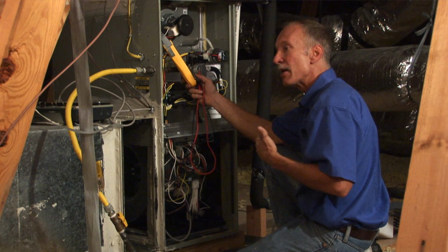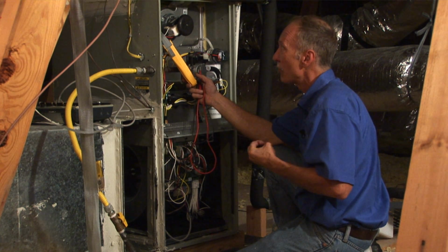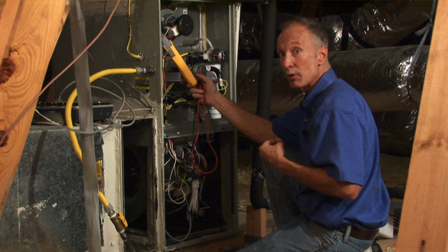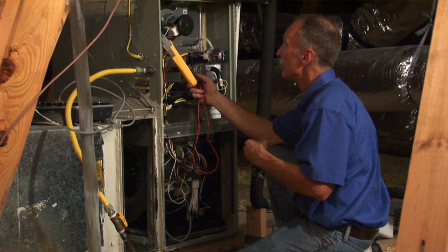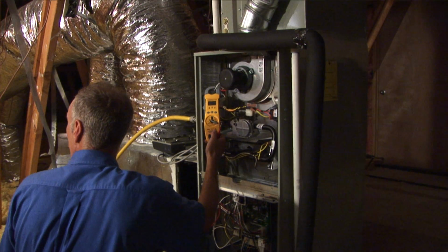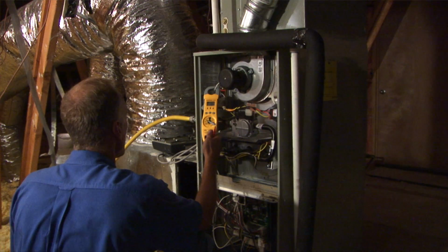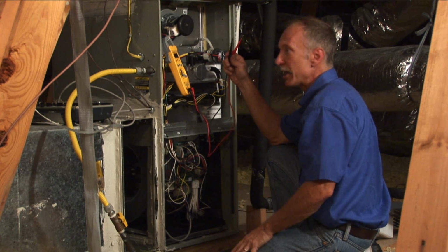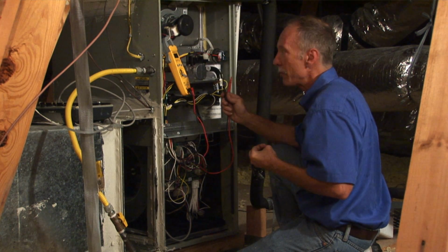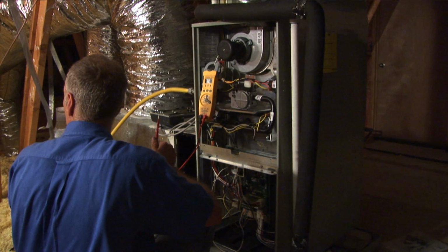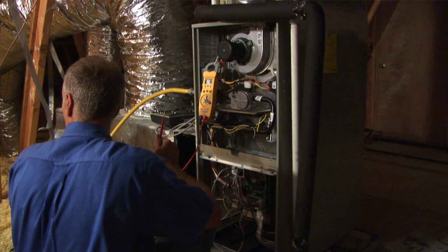And the whole idea of doing a furnace inspection is that we want to try and avoid any possible or potential problems down the road. Looks like everything's okay here, so I'm going to go to the next step. Now, if there were an issue and I was actually troubleshooting a problem, then I would use these probes, which are for the voltage probes.